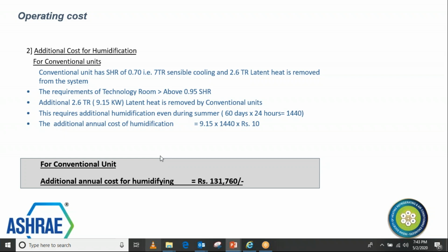Another important point which you have to note here is that in comfort air conditioner, humidification is not built in the system, in conventional or even in packaged conventional systems. It is not built in. So it's a separately installed humidification or a heater. This separate humidification system will work independently, does not know what is happening in the room other than the RH which it is trying to control. So your conventional unit is working independently.